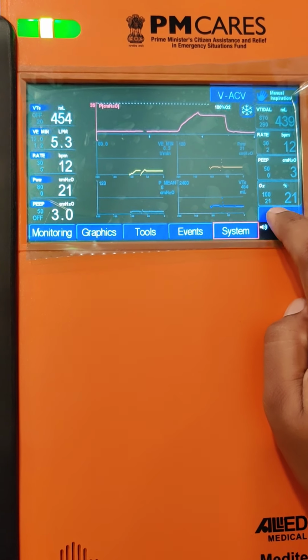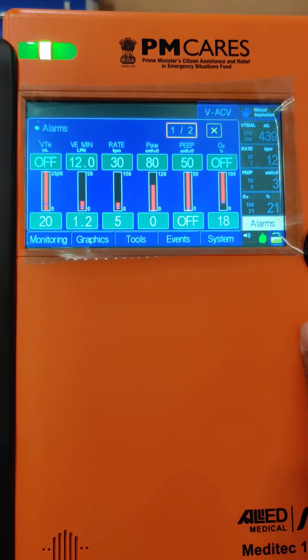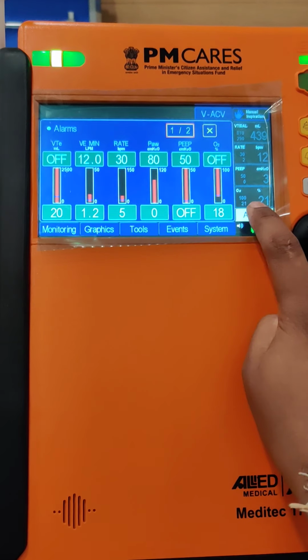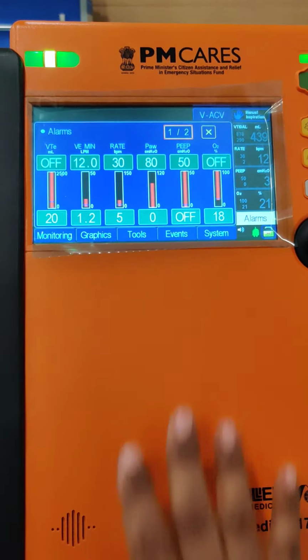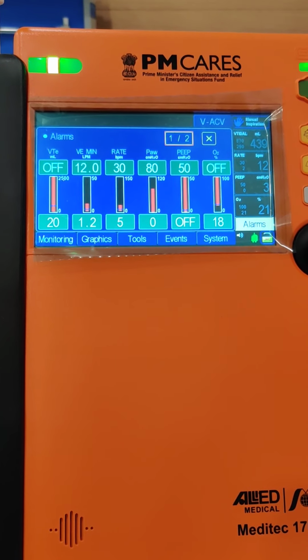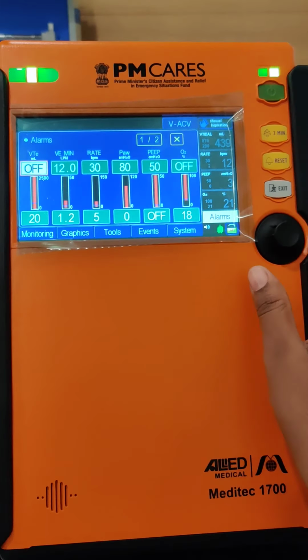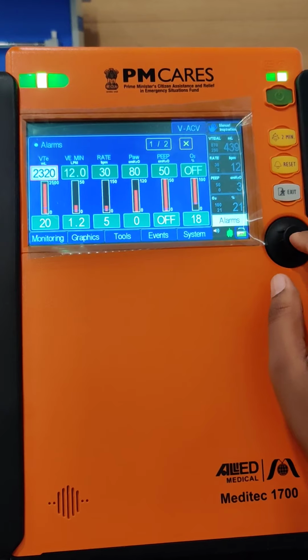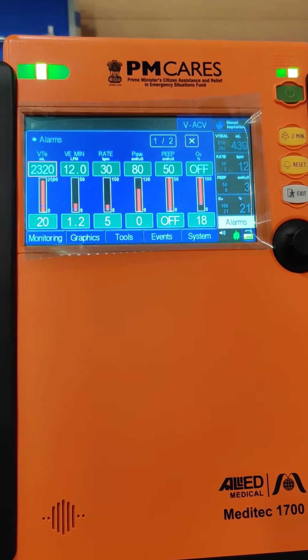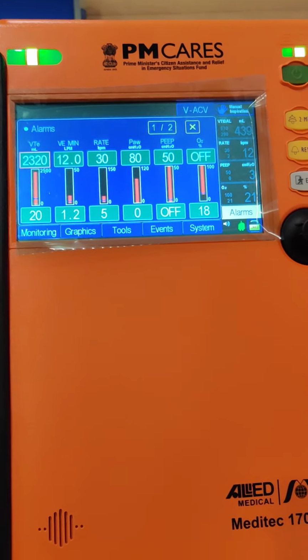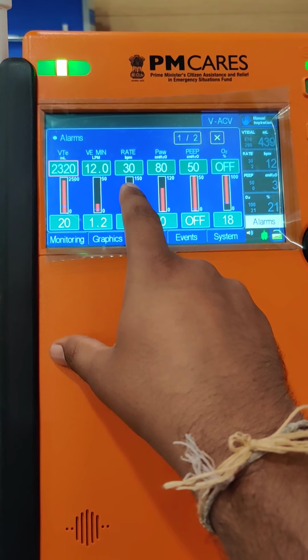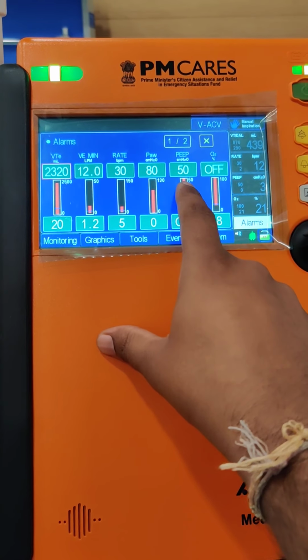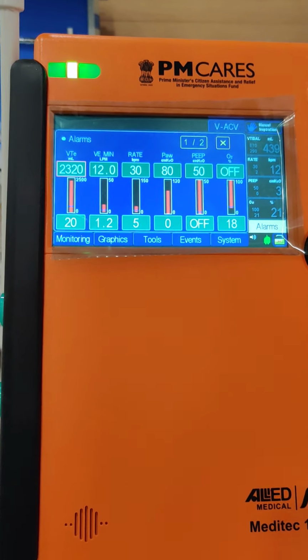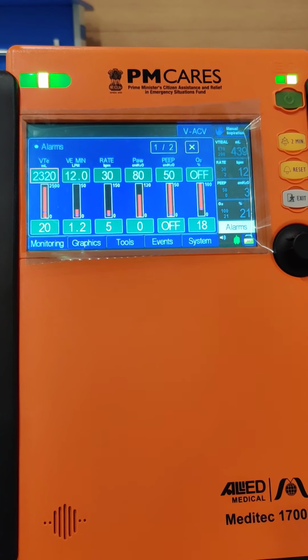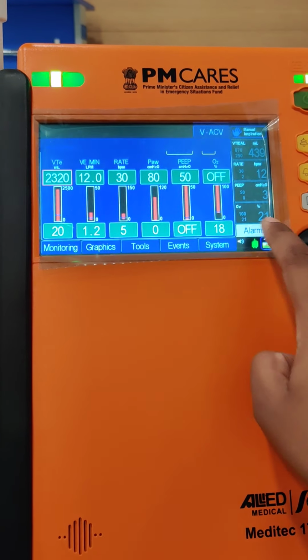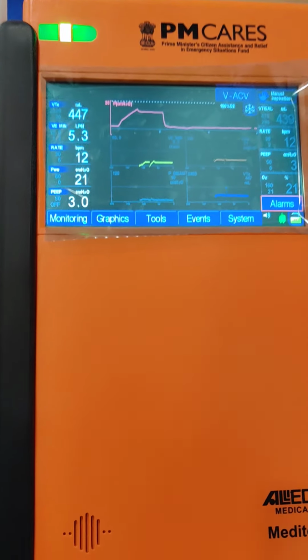Now the last shortcut key which is given over here is alarms. Whenever you touch alarms, you will get the window of all the alarm parameters, and the upper limit and the lower limit you can select as per the requirement. So we have given alarm settings for tidal volume, minute volume, respiration rate or frequency, airway pressure, PEEP and FiO2. You can set both the lower limit as well as the upper limit of the alarms from this window.